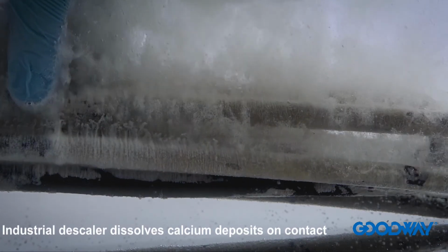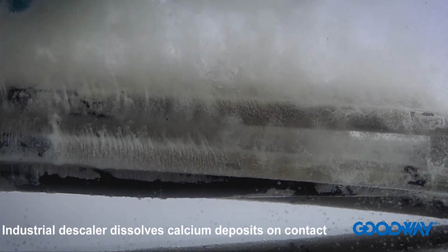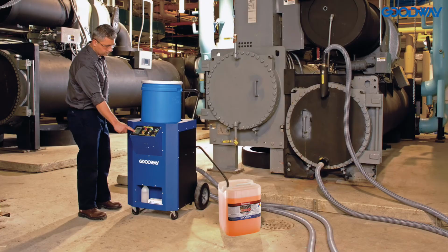Removing scale can become somewhat complex at times. However, if we know it's primarily a calcium carbonate deposit, it's removed simply by performing a circulation of that piece of equipment. We would pump into the bottom and return the fluid out the top.